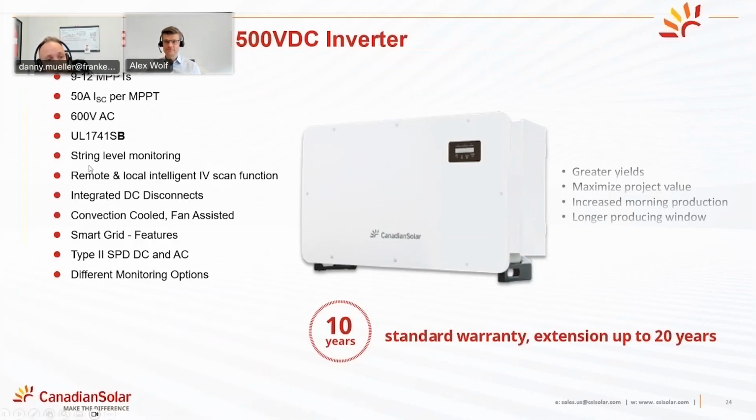We will have string level monitoring with these inverters. That used to be a pipe dream back in the day, back in like 2012, 2013. I remember selling projects back then and being asked all the time about it. It's become pretty standard now for modern inverters to have this, and this inverter also has string level monitoring. You can do a remote and local IV curve scan function, sorry. It has an integrated DC disconnect. It's convection cooled with fan assist, reducing the amount of fan that's required because it is convection cooled. It has a lot of smart grid features. Then we have Type 2 surge protection, DC and AC side, and there are a number of different monitoring options as well.